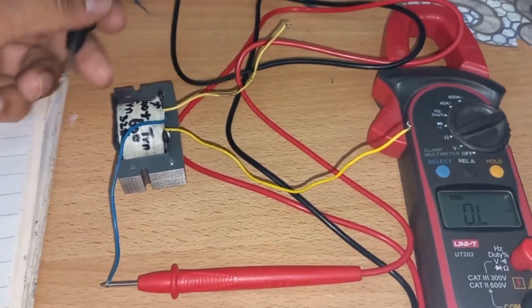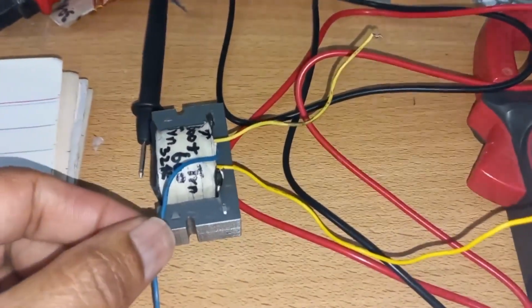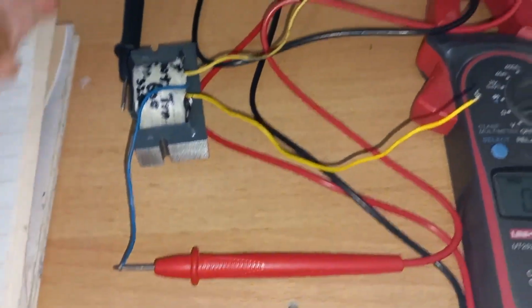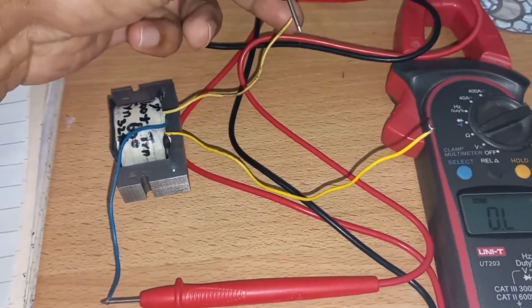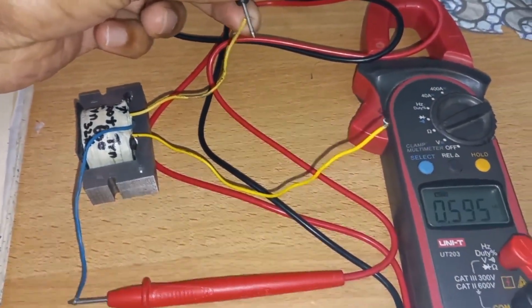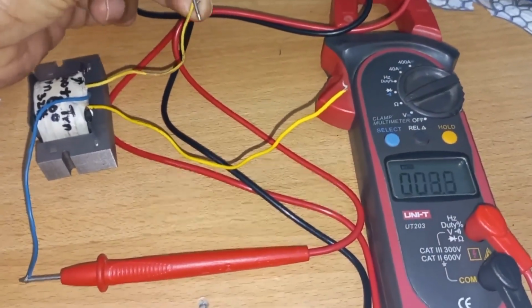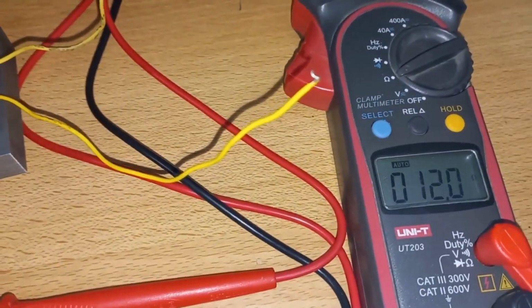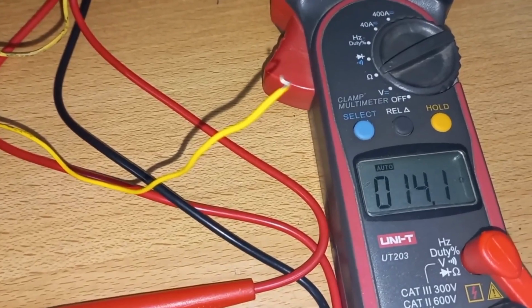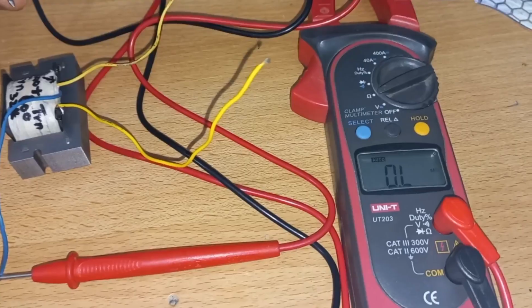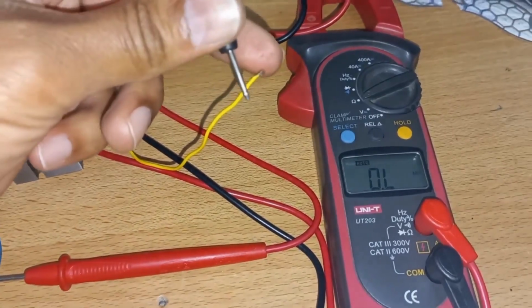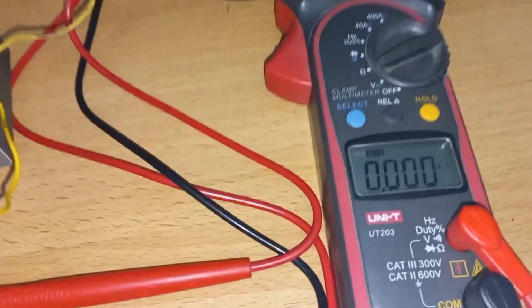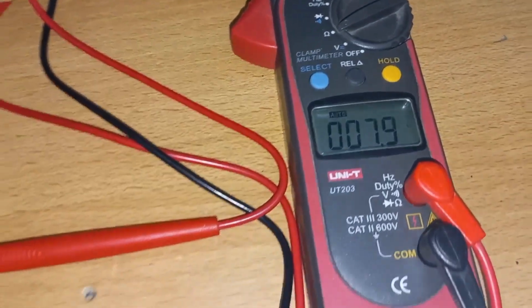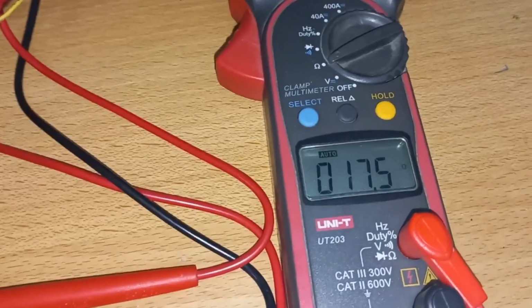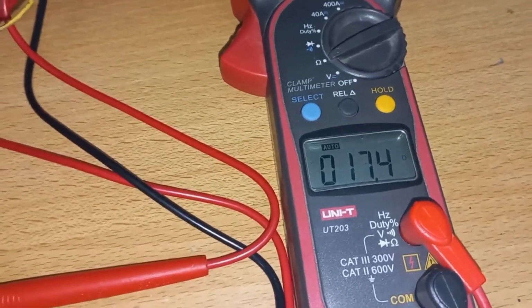Here I observe one more point. This blue is the common center point, so I connect the red wire, and if I connect the black one here, it gives us 14.6 or 14.1 ohm resistance. And from the center point if I go to the last point, it gives us 17.5 or 17.6 ohm.